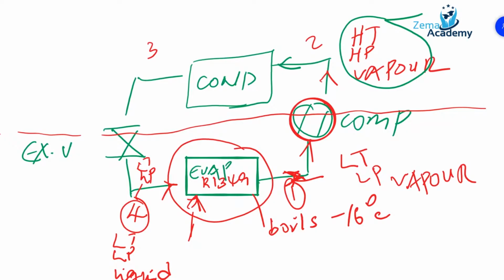By passing it through the condenser, you're rejecting, you're sinking that heat. Here you will have a secondary circuit to remove the heat from the condenser. And again, we will look at whether you're using air or water to remove the heat from the condenser. And that's how a condenser is classified, as either an air-cooled or water-cooled condenser.